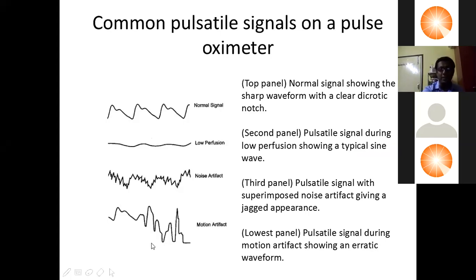And the third picture is showing noise artifact. This noise artifact is created when you loosely fit the SpO2 probe over the hand of the patient. And the fourth one, which is most important in pediatrics, is motion artifact. This motion artifact is a big problem for pediatric and newborn patients, because this age group moves their hands very frequently, and with hand movement the accuracy of the SpO2 is lowered. To correct this, there are different patented technologies, like Nellcor and Masimo have their own patented technology for modifying this error.